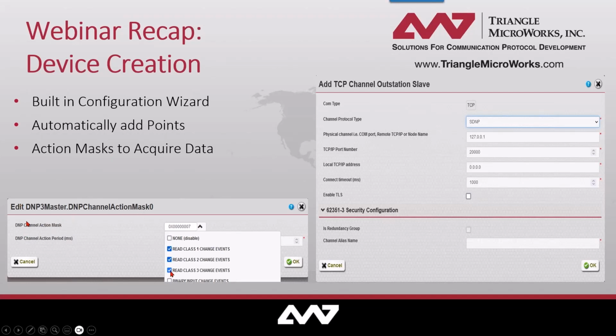Following the example I was just talking about, we'll have a DNP3 master action mask. The action mask tells the gateway how you want to receive the data—do you want it polled periodically every second, are you enabling unsolicited messages so you get them as they change, or are you expecting an integrity data pull every 24 hours? However you want to get the data in, you can configure the gateway to do it.